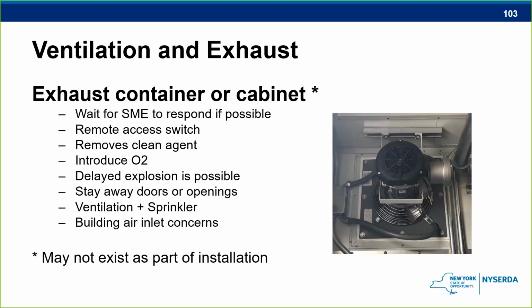But to tell you that there couldn't be a small little explosion inside the cabinet itself, like the cabinet that Jennifer showed you before, if something got caught in the interior of that, would there be a pocket in there that could cause a little bit of an explosion? Yes. How bad is it going to be? I don't know. But if people are going to put these exhaust fans inside of those enclosures, you want to have remote access. We don't want the firefighters walking right up to the enclosure itself to activate that thing, because once it starts pulling, it may bring the mixture down into its flammable range and cause an explosion to take place. What is my ignition source? An internal short circuit, which could be anywhere within that system itself.